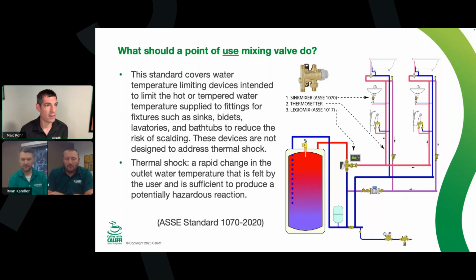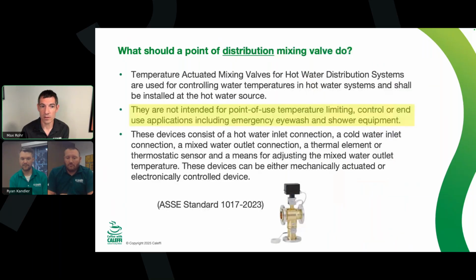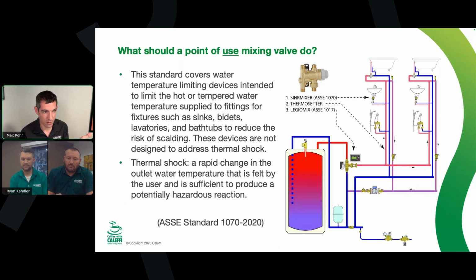One misconception with these mixing valves is you could get a point of distribution mixing valve and set it to 113 degrees, how ours comes out of the box. But it's not going to shut off 3-inch flow fast if you lost the cold pressure. There's a lot of inertia in that much water flow, which is why you won't see these bigger than like a 3/4 inch tailpiece on a point of use mixing valve, since it needs to react faster.